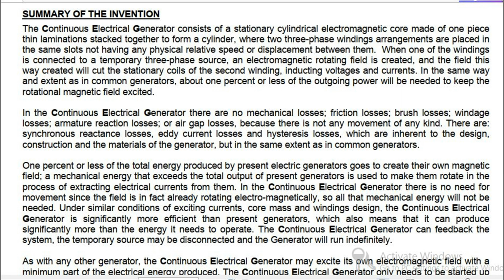Summary of the invention. The continuous electrical generator consists of a stationary cylindrical electromagnetic core made of one-piece thin lamination stacked together to form a cylinder, where two three-phase windings arrangements are placed in the same slots not having any physical relative speed or displacement between them. When one of the windings is connected to a temporary three-phase source, an electromagnetic rotating field is created, and the field this way created will cut the stationary coils of the second winding, inducting voltages and currents. In the same way and extent as in common generators, about 1% or less of the outgoing power will be needed to keep the rotational magnetic field excited.